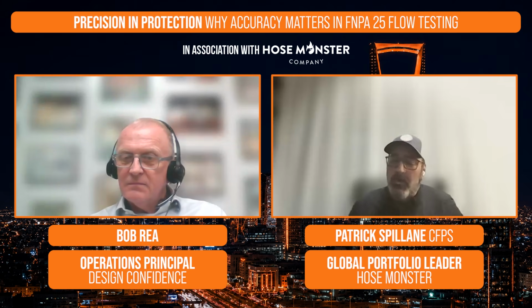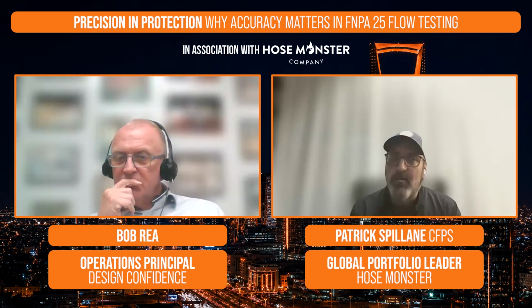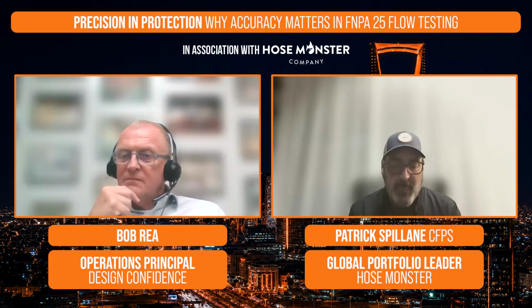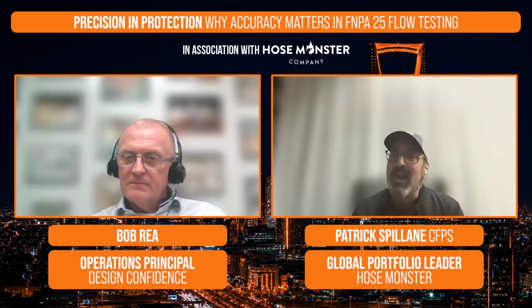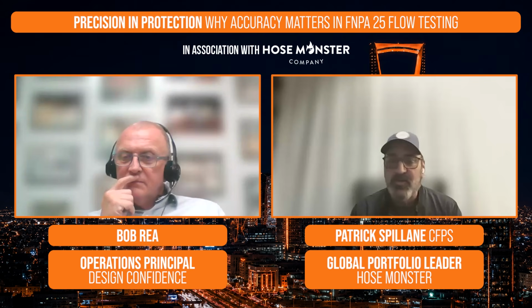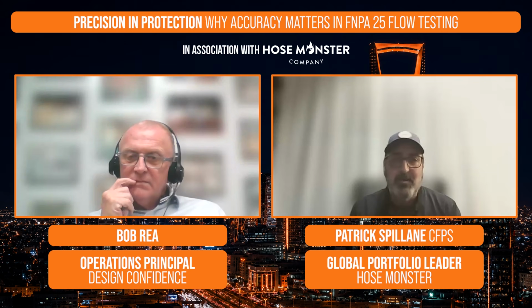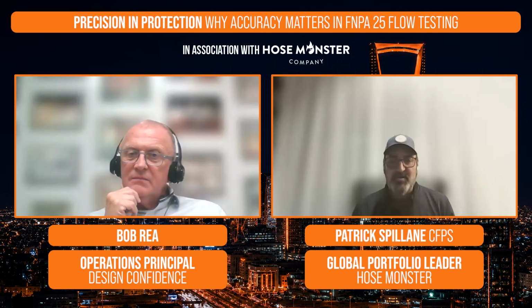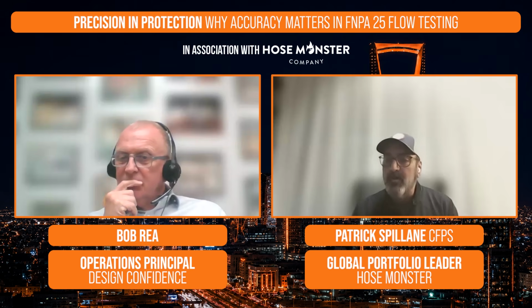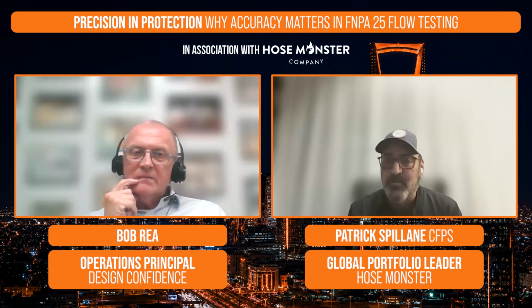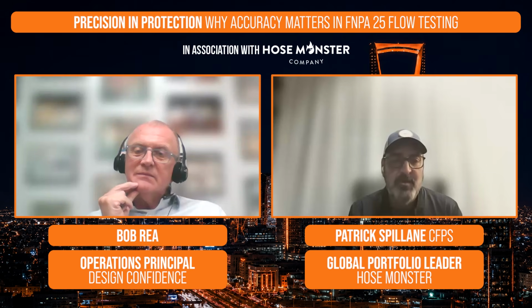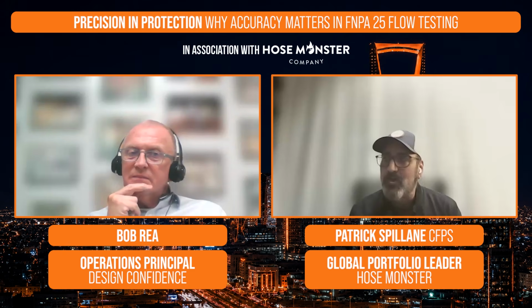There's the biggest things. When it comes to measuring the fire pump itself, we want to, again, it's that suction minus discharge pressure, our net pressure that's being created by that fire pump. We want to compare that to our placard of the fire pump. Per NFPA 25, we want to be within 95% of that churn pressure. For instance, if that max net churn pressure is 100 psi, we want to make sure our suction minus discharge is at least 95 psi or better, to be closer to that churn pressure, so that it's providing enough adequate pressure.